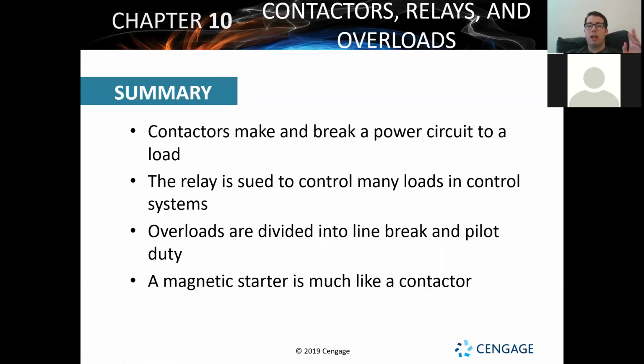All right, so keep in mind, again, relays, contactors, magnetic starters, especially relays and contactors, those right there, same thing. Only difference is contactors handle a much higher load, relays handle a much smaller load. All right, so smaller motors, relays. Big motors, contactors. By big motor, I just mean even a residential compressor. That's going to need a contactor that is not going to run off of a relay.